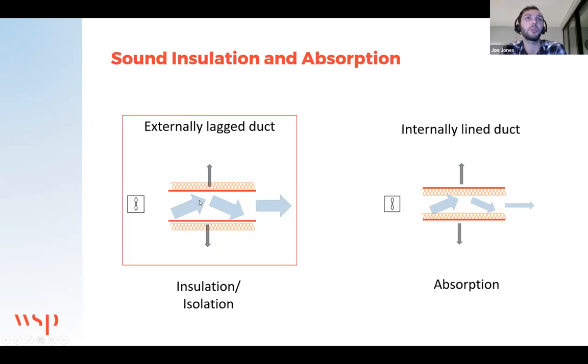So I'm sure you're familiar with either externally lagged ductwork or internally lined ductwork. These can be done, well, externally could be done for thermal reasons, but just looking at the acoustic reasons here, externally lagging ductwork, and usually, although not shown here, you'd have perhaps a polymeric mass barrier on the outside of the duct. Lagging on the outside of the duct is for insulation or isolation of the sound. So having additional mass in the outer barrier or in a material helps contain the noise within the duct. And this could be, for example, a wall in a building, but sticking with the duct example here, it helps contain the noise within the duct, which obviously protects any environment outside of the duct from the noise.